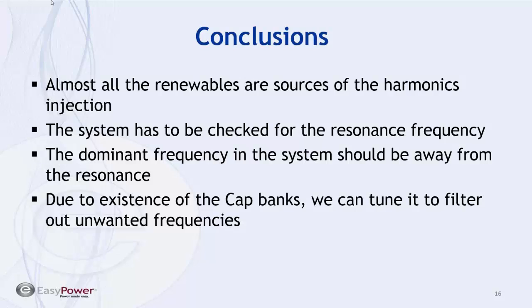And eventually, with this slide, I conclude the presentation. What we covered here was in fact the continuation of another webinar that I had done in the past. So I put the same system together. I came up with a formula, which is a popular formula in harmonic systems. I used EasyPower to calculate the resonance frequency of the system.